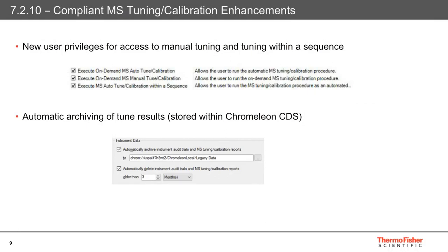In addition, we've also added some new user privileges for access to manual tuning and tuning within a sequence. These prevent inappropriate use and restrict access to the tune function for insufficiently trained users. It's also possible to define automatic archiving of the tune results, which works in an identical fashion to the archiving of instrument audit trails, and is found in the same location via the Chromeleon global policies in the Chromeleon administration console.